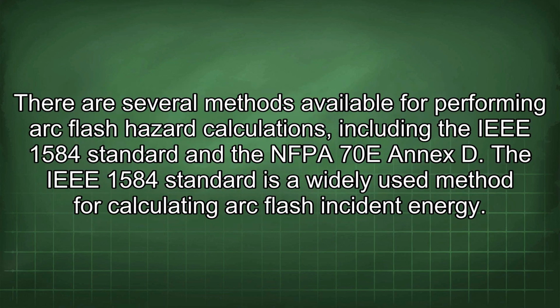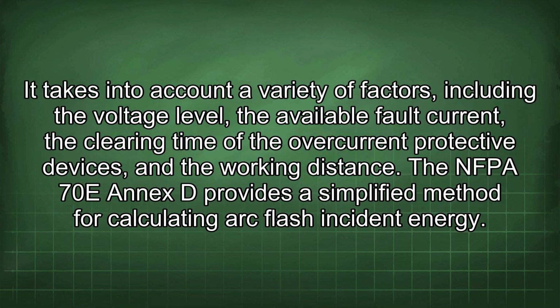There are several methods available for performing arc flash hazard calculations, including the IEEE 1584 standard and the NFPA 70E Annex D. The IEEE 1584 standard is a widely used method for calculating arc flash incident energy. It takes into account a variety of factors, including the voltage level, the available fault current, the clearing time of the overcurrent protective devices, and the working distance.